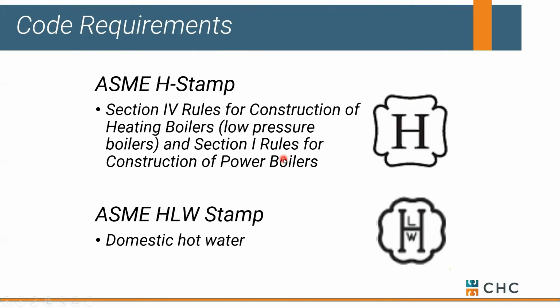A boiler is designed for a closed loop heating system, and it carries an ASME H stamp. There's also controls and safety devices that are rated for a boiler. A water heater carries a different stamping from ASME. It's called an HLW stamp, and the materials tend to be non-ferrous. Okay, anything that's heating domestic water, you're typically looking at some type of copper, bronze, stainless steel. Where on a regular boiler, you've got a lot of iron construction designed for a closed loop system that's chemically treated, and there's not a lot of corrosion occurring.